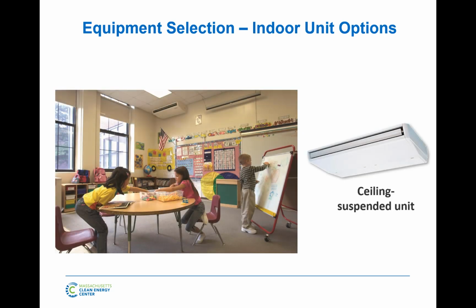Next up, we have ceiling suspended units. So this is still a ductless unit, just a little bit different form factor. I see these used a lot in kitchens, classrooms, and wide open spaces, something like this. They're physically a little bit bigger. You can see it up in the corner there. Because they're bigger, they have bigger fans, and they have the ability to throw air farther. So this can throw air about 30, 35 feet down a wall. Perfect for this corner here.